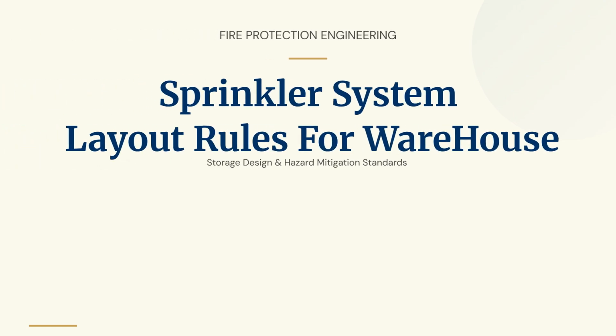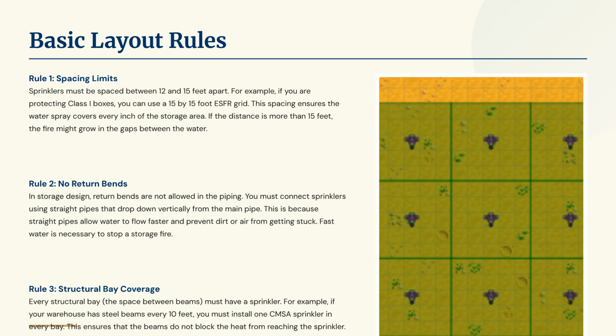This video covers fire protection engineering, focusing on sprinkler system layout rules for warehouses, including storage design and hazard mitigation standards. Rule 1 requires sprinklers to be spaced 12 to 15 feet apart to ensure coverage. Rule 2 prohibits return bends in piping for faster water flow. Rule 3 mandates that every structural bay must have a sprinkler to prevent heat blockage by beams.